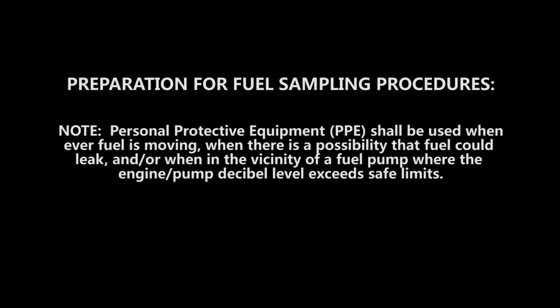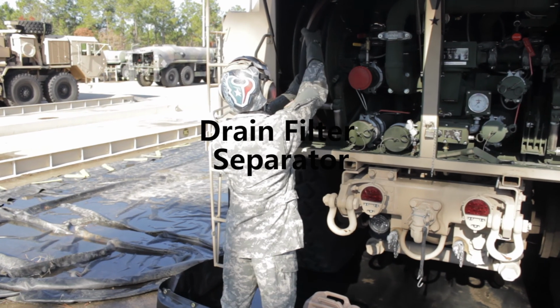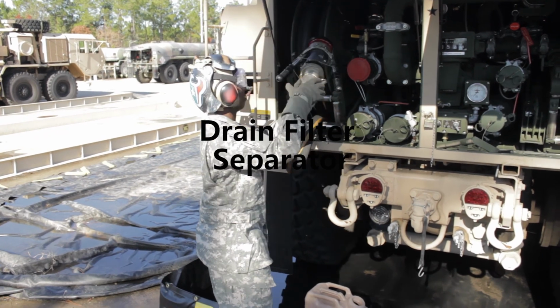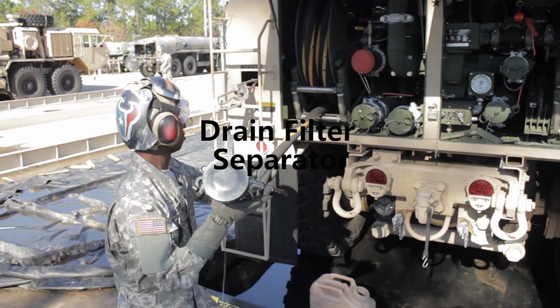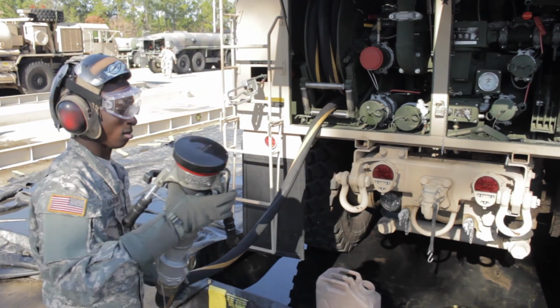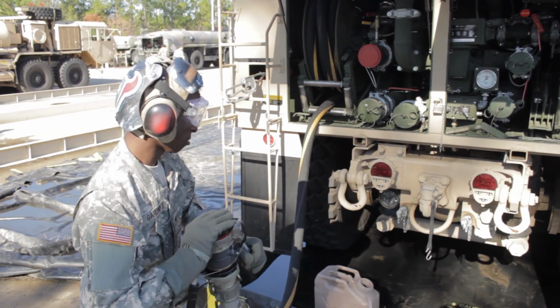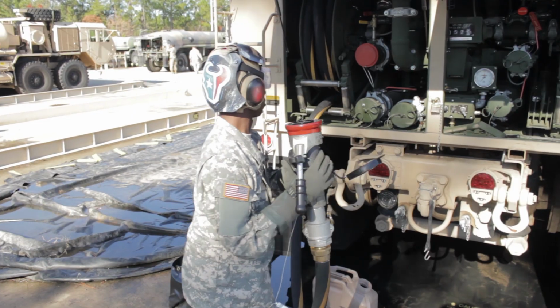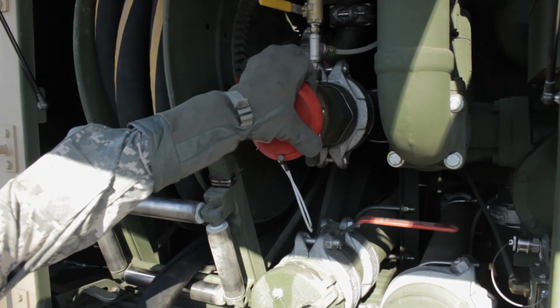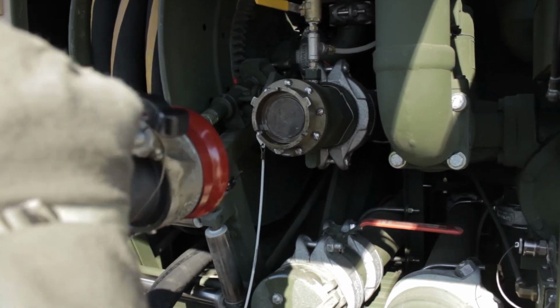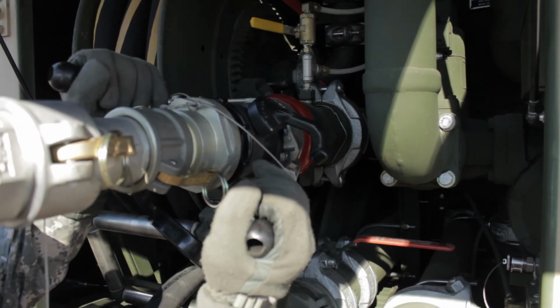Personal protective equipment, PPE, shall be used whenever fuel is moving, when there is a possibility that fuel could leak, and/or when in the vicinity of a fuel pump where the engine pump decibel level exceeds safe limits. Pull out enough of the fuel hose to attach the D1 fueling nozzle to the D1 receptacle. Rotate the lever forward on the D1 nozzle.